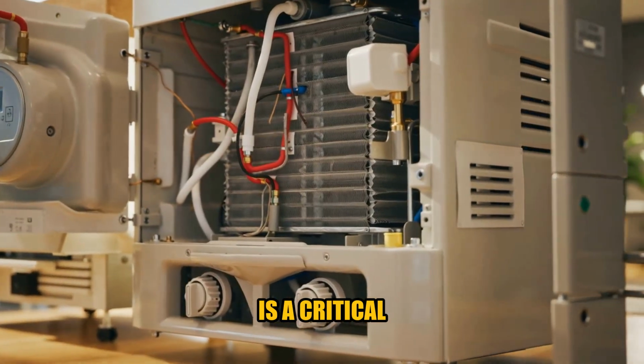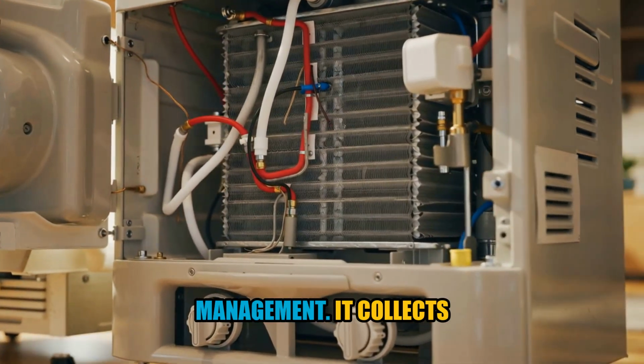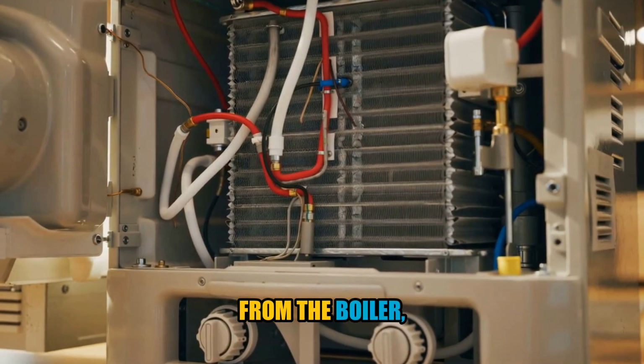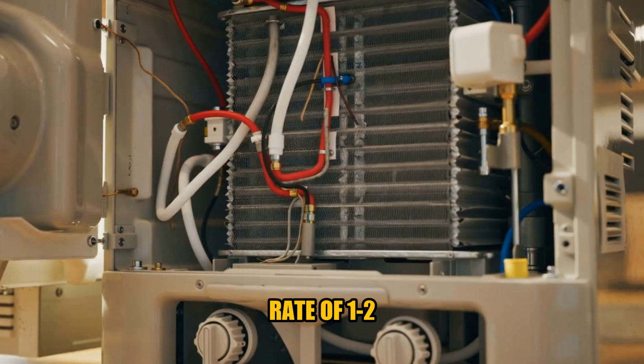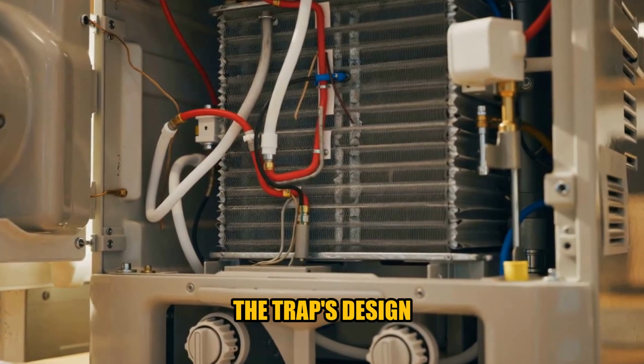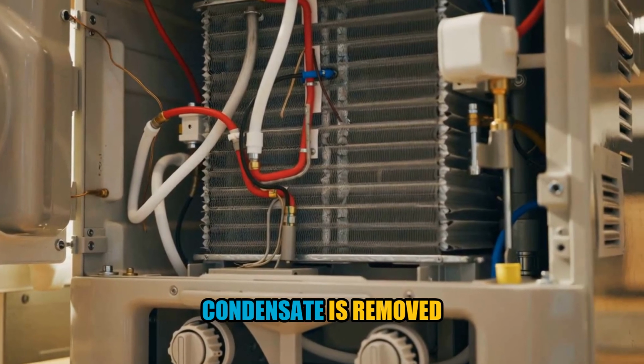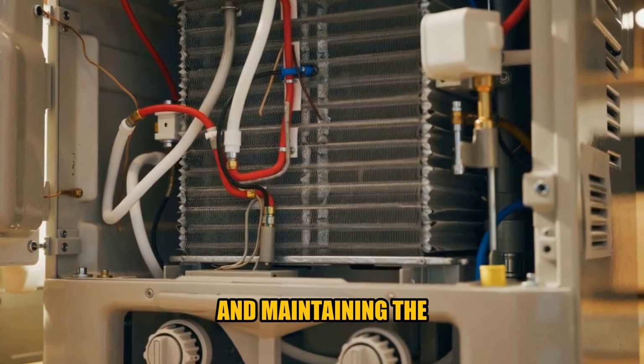The condensate trap is a critical component in condensate management. It collects and removes condensate from the boiler, typically at a rate of 1 to 2 liters per hour. The trap's design ensures that the condensate is removed efficiently, preventing blockages and maintaining the boiler's performance.